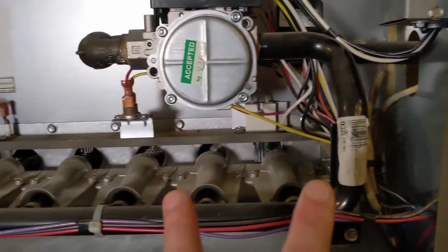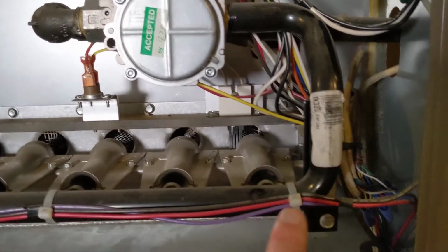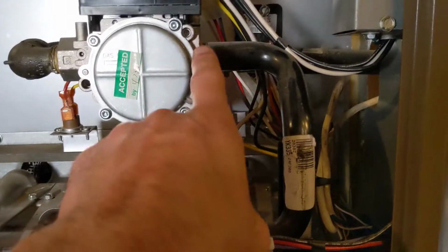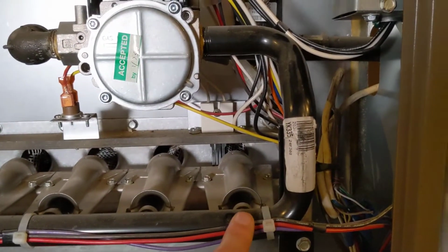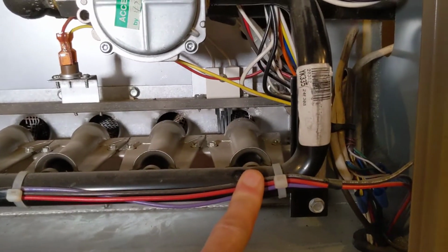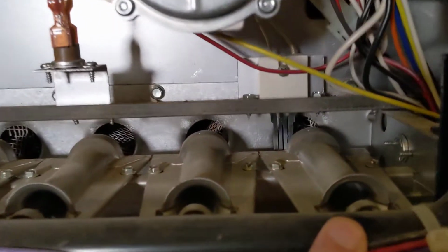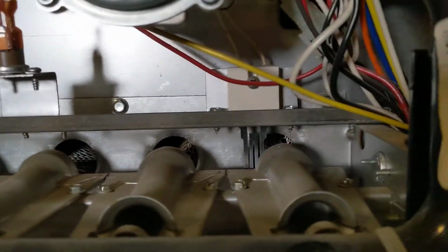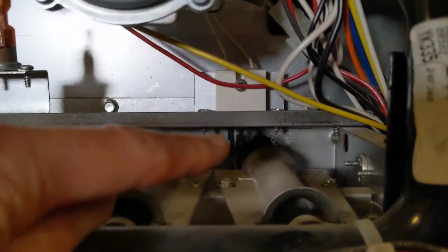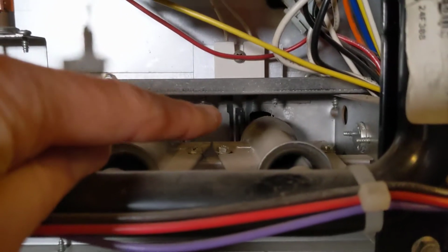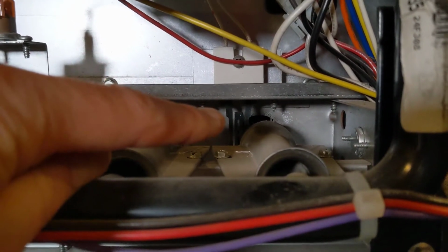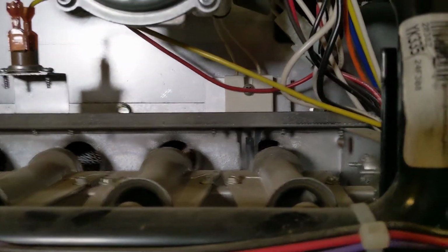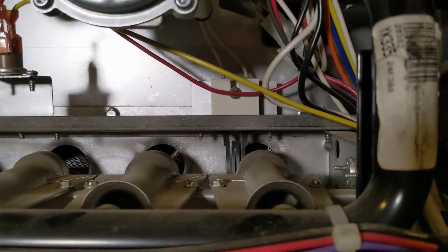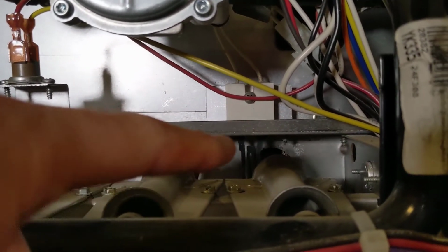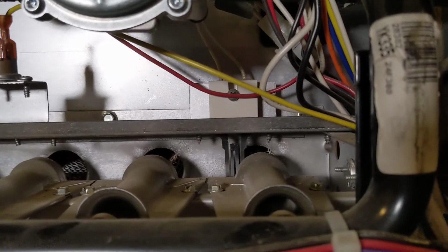Now there's a couple components to ignition. The first one being, if you trace the tube out of the gas valve, you'll notice that it hits one of your combustion jets first. Now notice behind there, the difference between that jet and a lot of the other ones is it has that little apparatus there. Do you see that? I'll show you that in a minute. That's your igniter. So the next thing that's going to happen is gas is going to start flowing, and then that thing is going to glow red hot to ignite the gas.